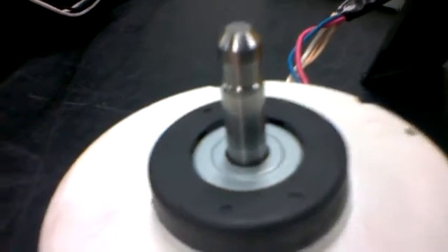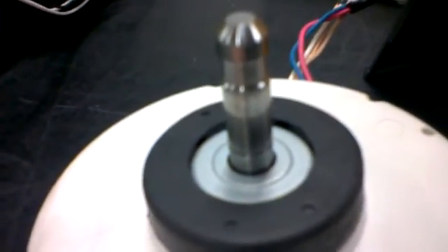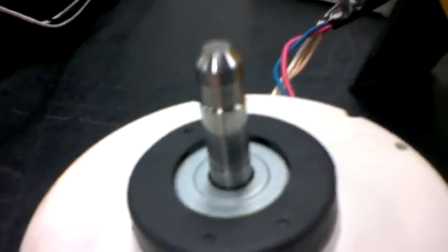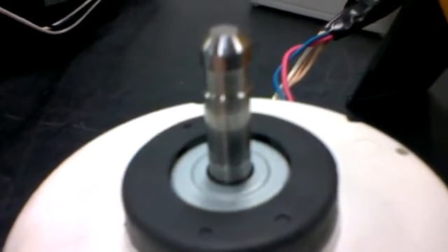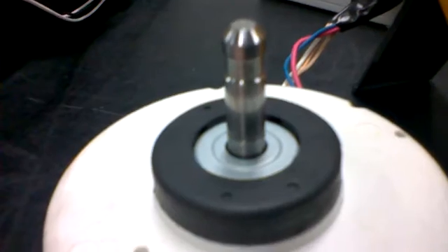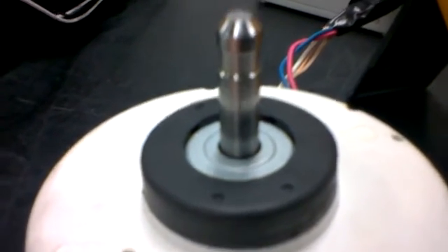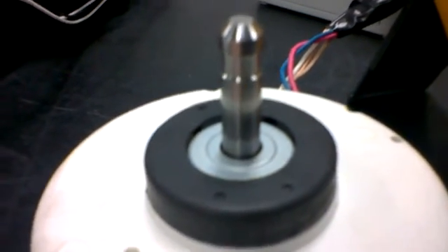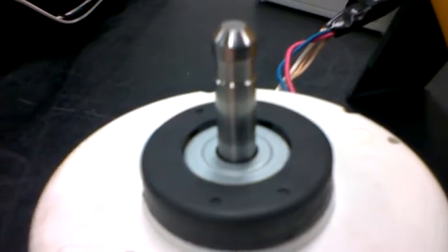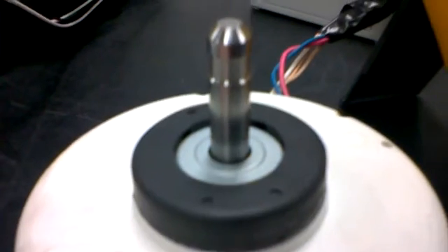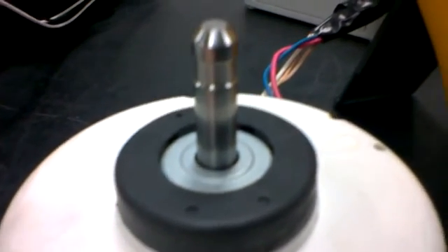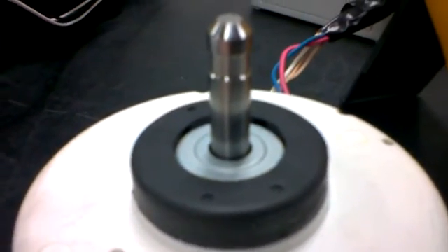Now the PCB won't always shut the motor down immediately. It will actually continue to run on. It's actually just stopped now. In some cases, it may give it another go to try and restart, and if it still doesn't see the signal back, it will end up bringing a fault on the PCB itself. You'll see it's trying to restart the motor now, and that's what I like about this quality gear. It always gives it a second go to make sure things are okay. And when it fails to see the signal, it will shut it down.